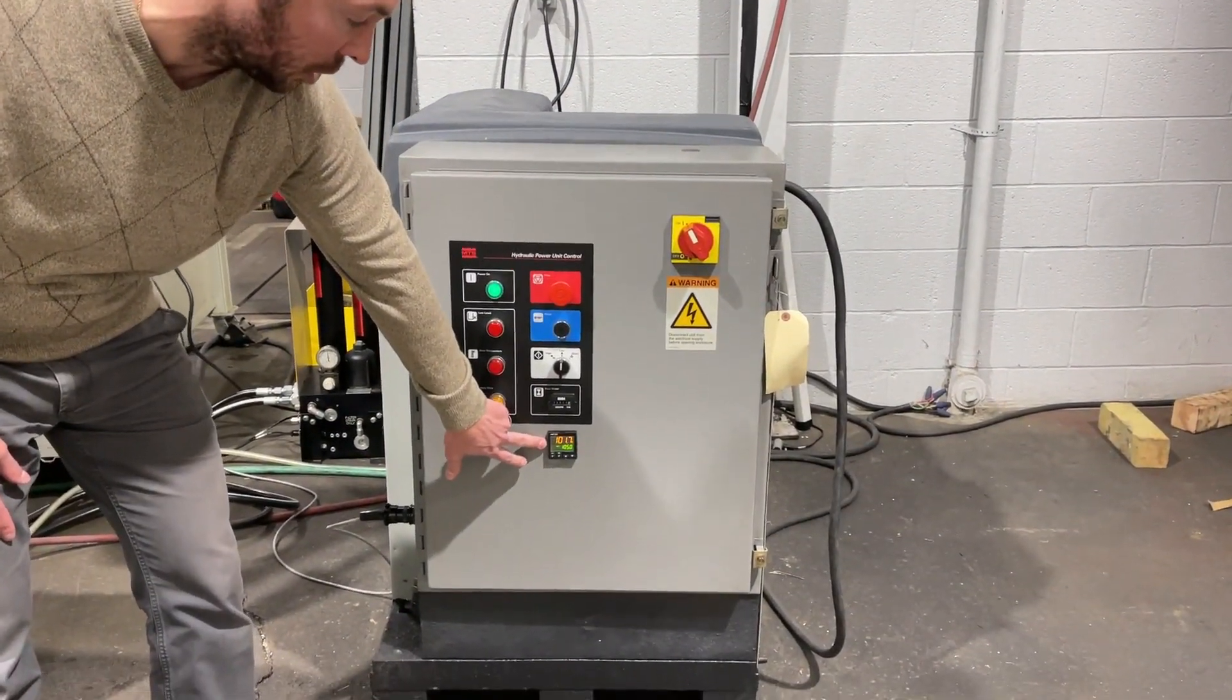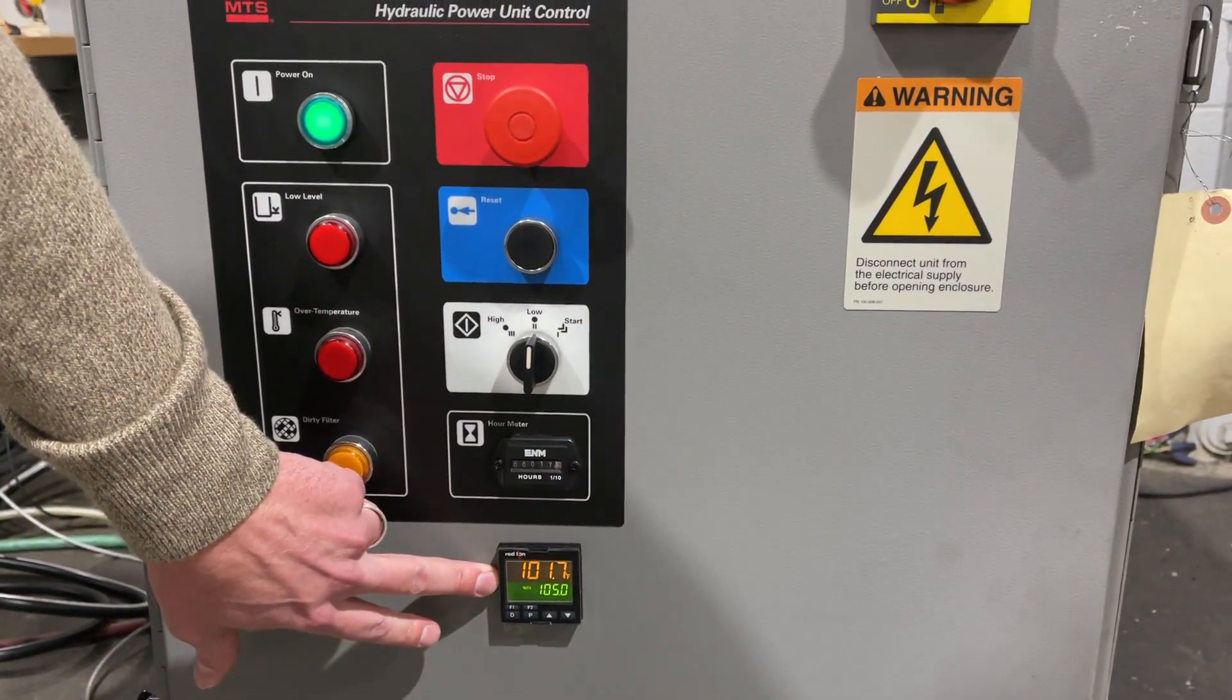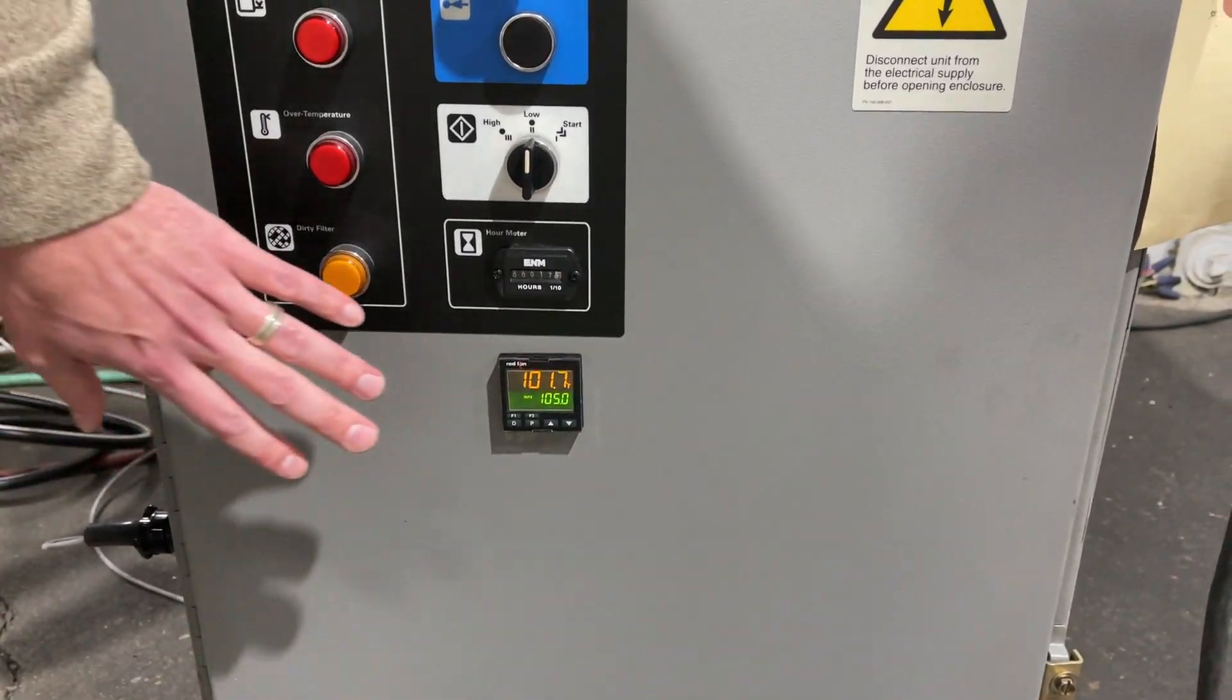Retrofitted with our temperature controller, so you always know what your hydraulic temp is and it's always going to PID control to that temperature setting we have programmed in it.